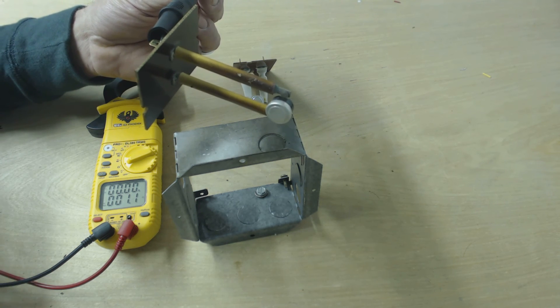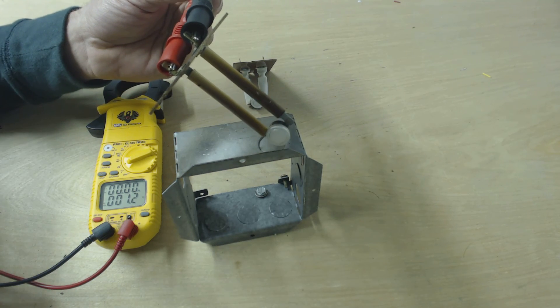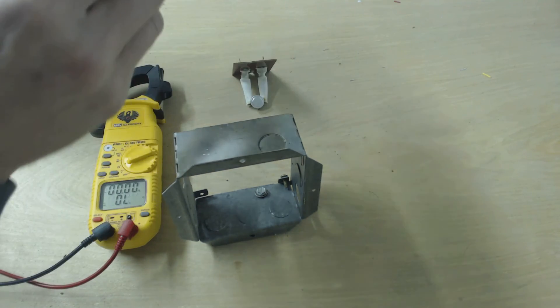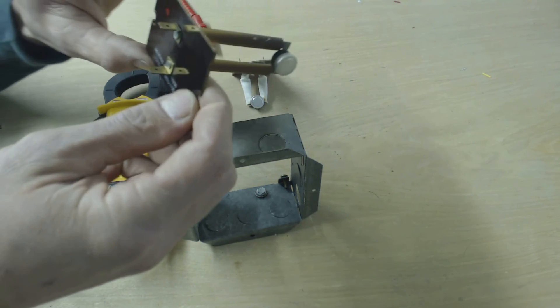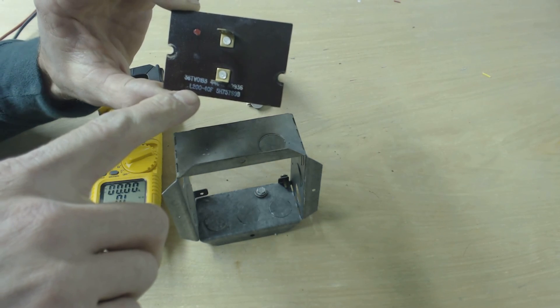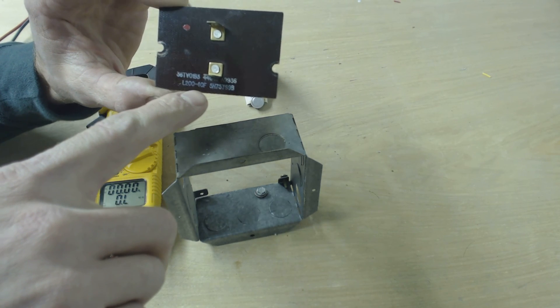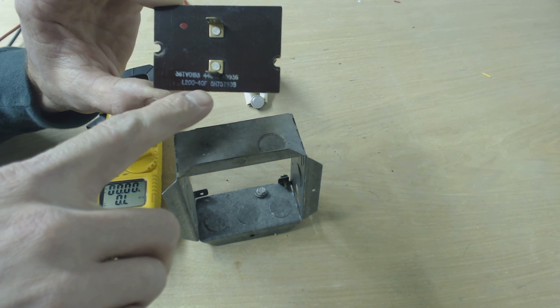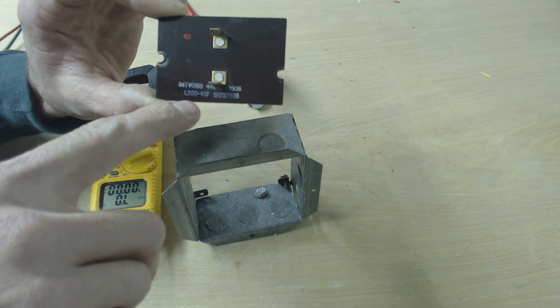Anyway, it did just go ahead and close again. So this one is supposed to be opening at 200 degrees and closing back down at negative 40 below that, which would actually be 160 degrees.